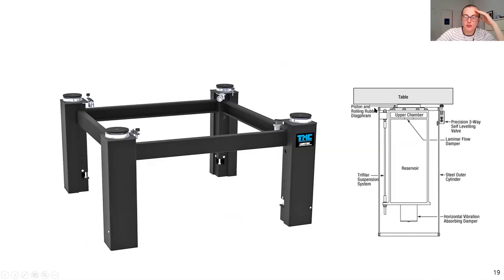You can see that there's these little paddles here where this foam portion would be in contact with the table. In this cartoon here these sensors are touching the table and they're on a lever. If you push on the table it will detect that change in the distance and then it will have this reservoir of some gas here. It'll push on a piston or a rubber diaphragm. It's literally like a balloon that your optical table is sitting on and it will increase the amount of gas there and correct and push the table back up.